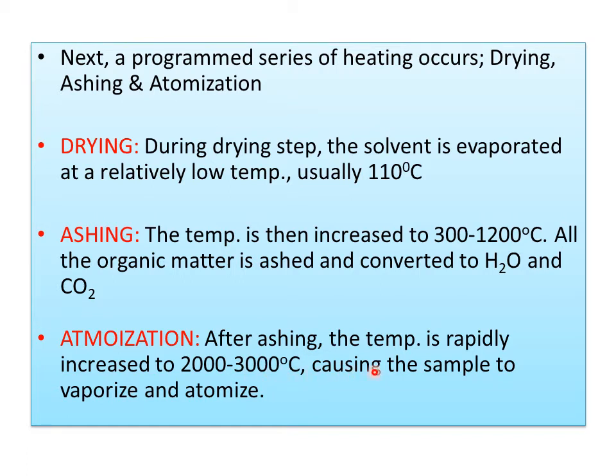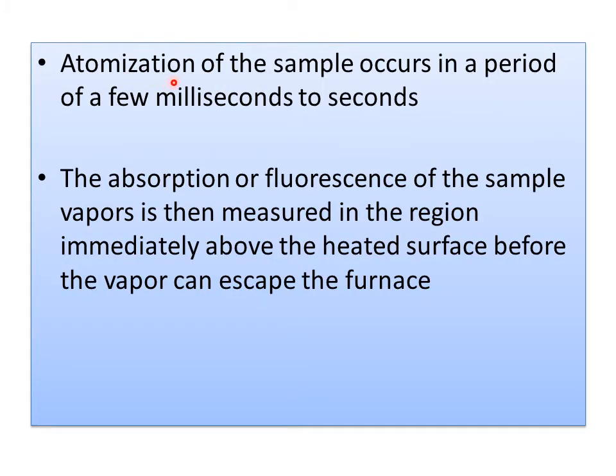The third step is atomization. After ashing, the temperature is rapidly increased to 2,000 to 3,000 degrees centigrade. At this high temperature the sample vaporizes and gets atomized. Atomization occurs within a period of a few milliseconds to seconds. The absorption or fluorescence of the sample vapors is then measured in the region immediately above the heated surface before the vapors escape the furnace.